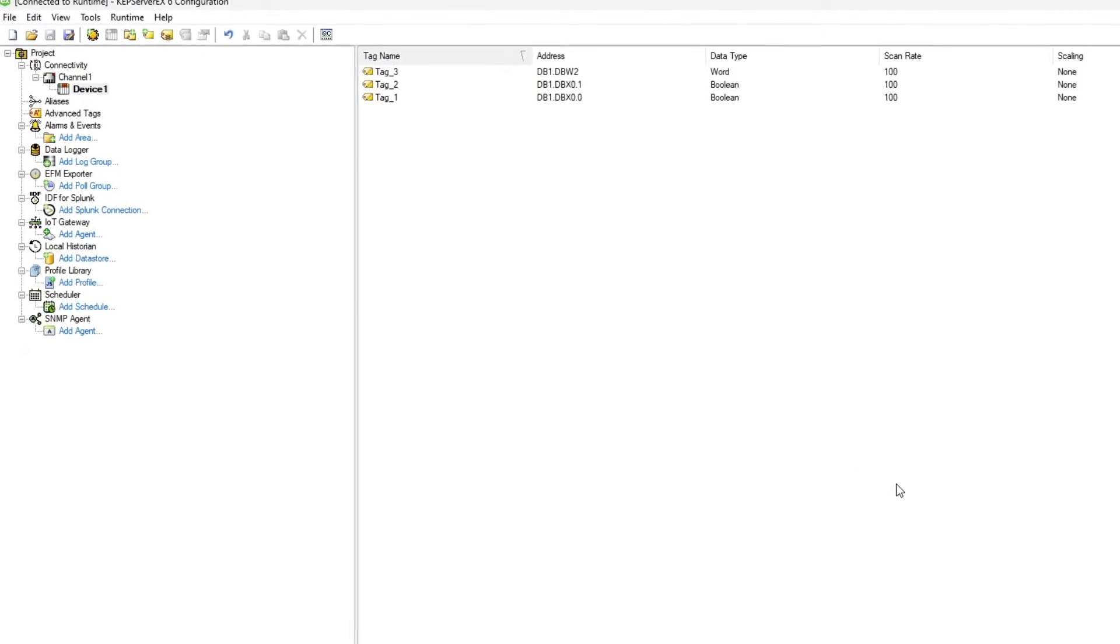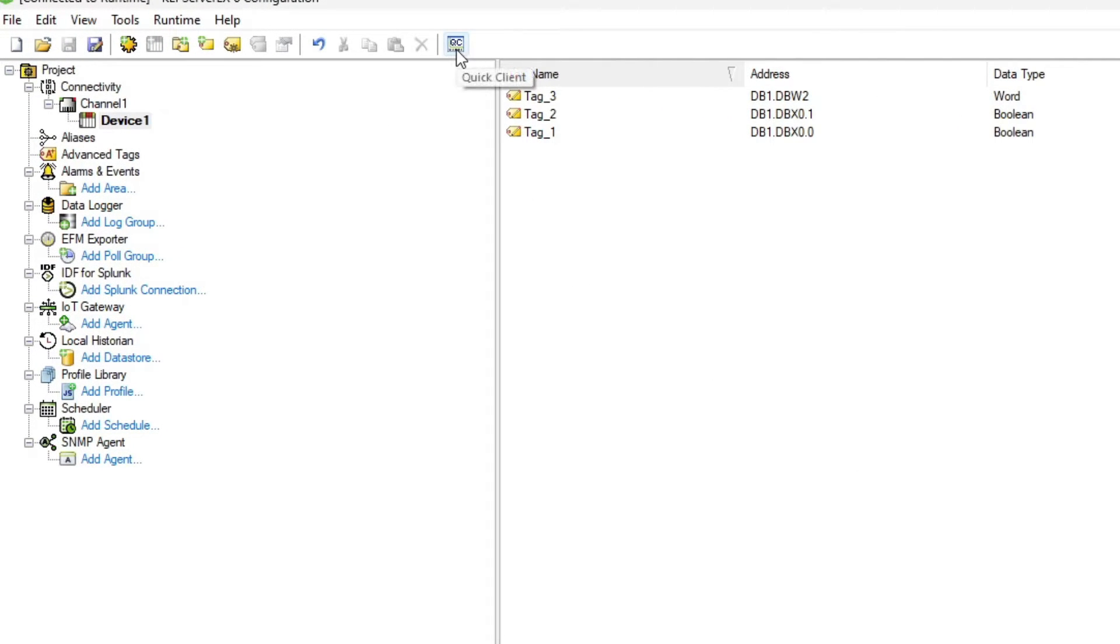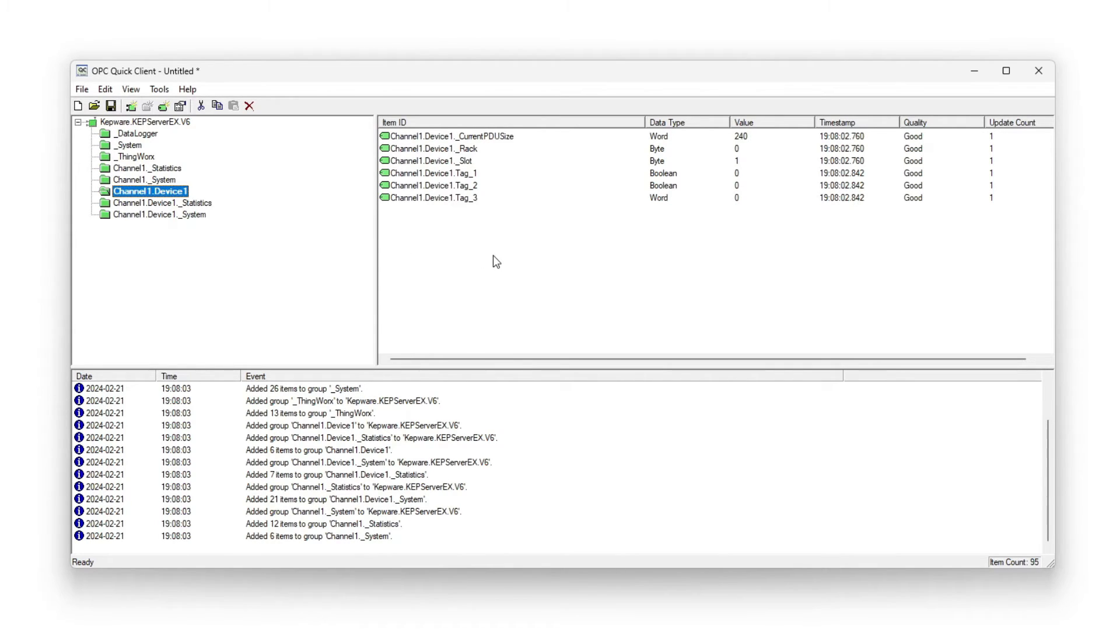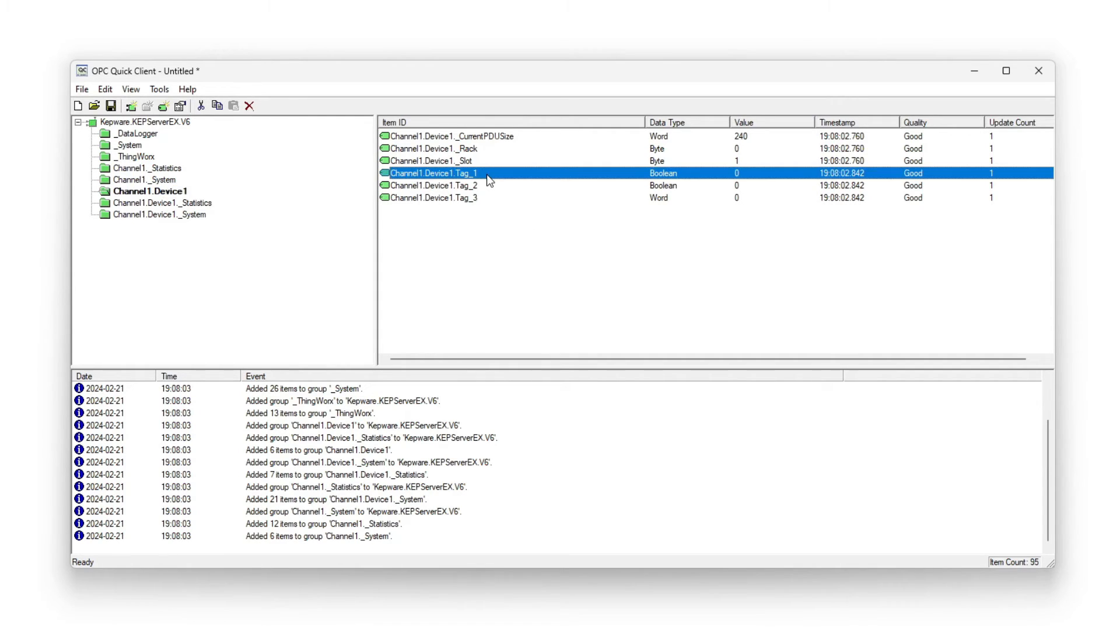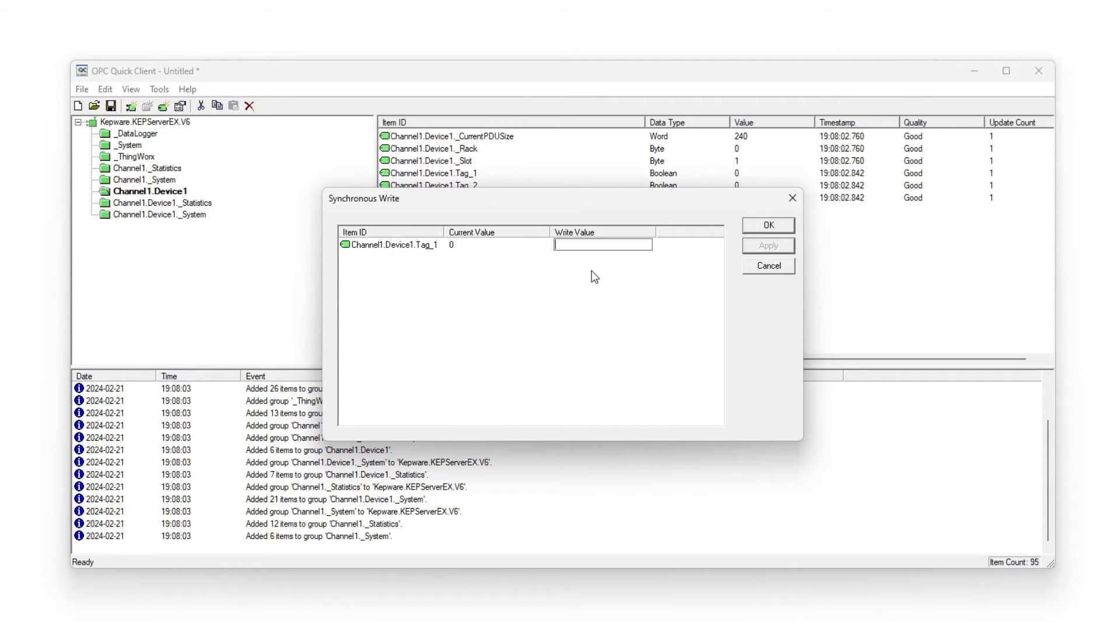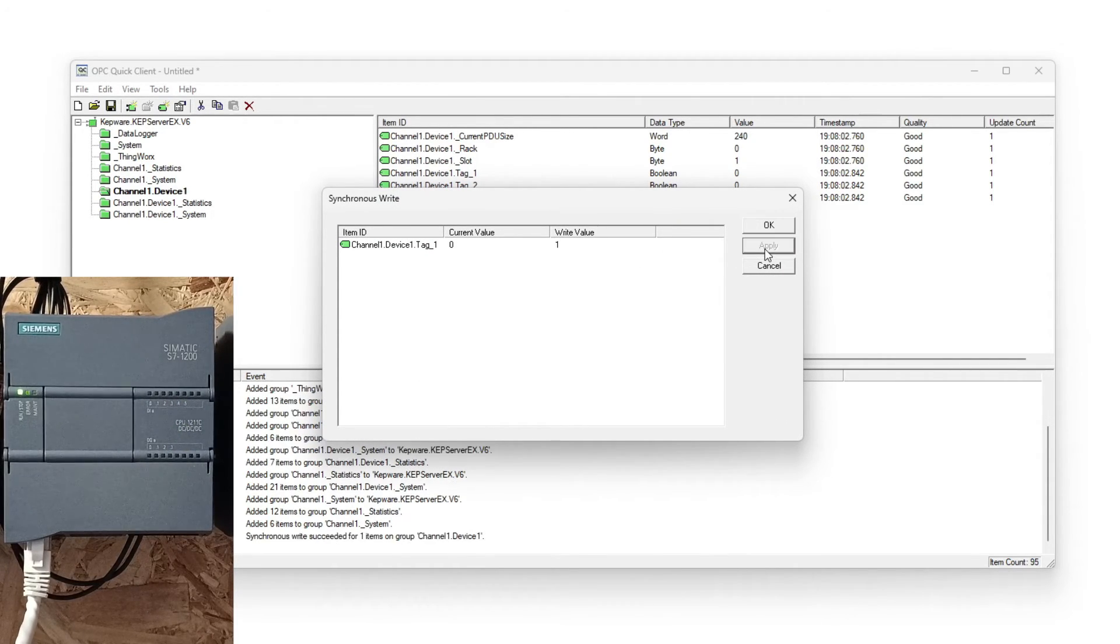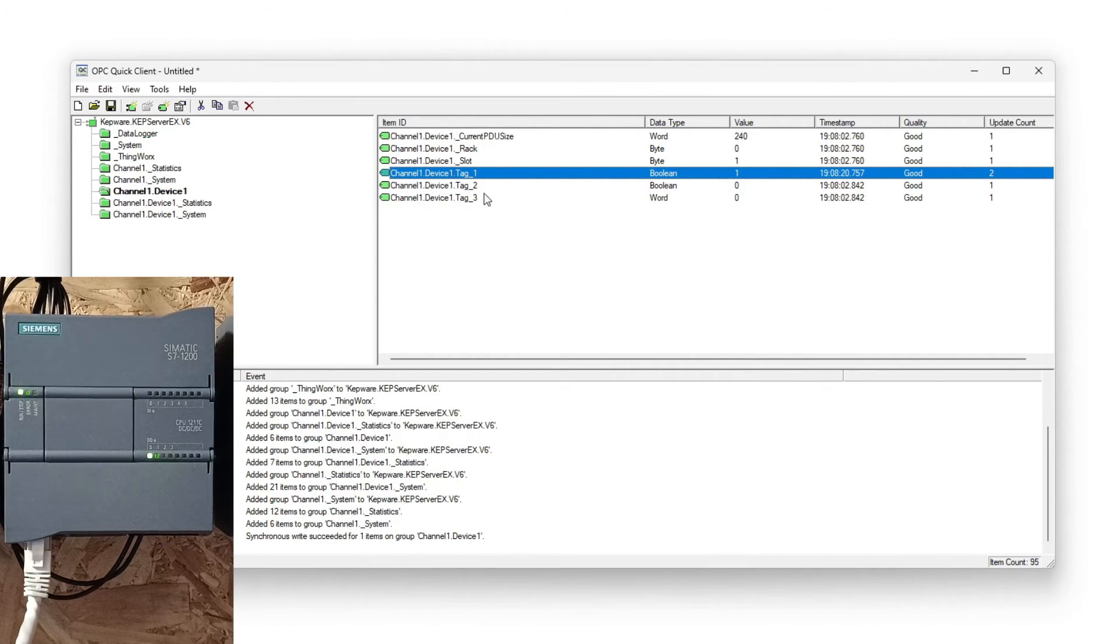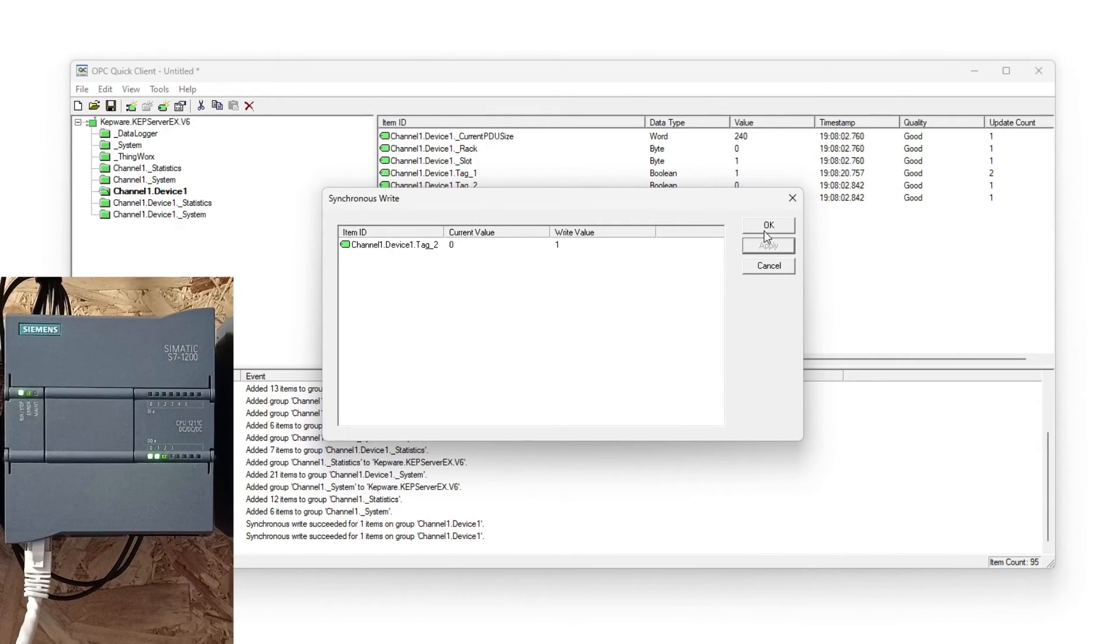Now to test out the connection we can click on the quick client button. Then we click on the column with our channel and device name. Here we can find all our three tags. If the quality column says good on our tags then the connection to the PLC works. To trigger our tags we need to right click on one of them and then click on synchronous write. Then we write a value and click on apply. I will test all the tags to see that everything works.